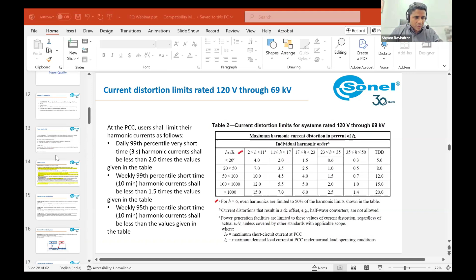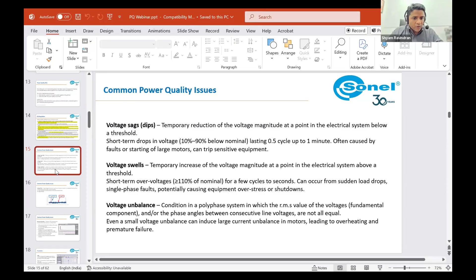I'll add one more point, which customers often ask about. If you notice my screen, one common power quality problem is nuisance tripping. I'm highlighting this because from a safety audit point of view, we do want this kind of tripping to happen, but if you don't have the right rated breakers, you'll get a lot of nuisance tripping, not just from a safety standpoint but also from a PQ standpoint. By breakers I mean not only MCCBs but also RCDs. The rating of that tripping has a major impact due to power quality issues. In any power quality book, you'll find nuisance tripping of breakers as one of the common PQ phenomena. There are two reasons: first, how redundant is our system?